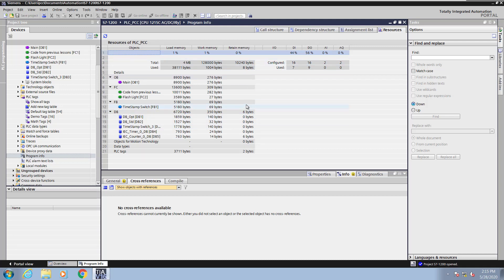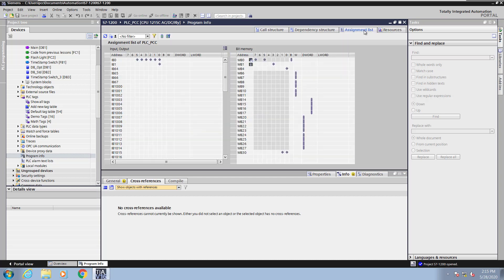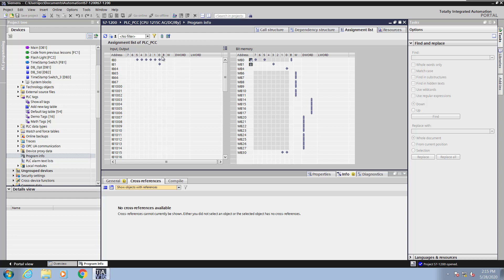Next I will select the assignment list tab. This is where you can see where your inputs, outputs, and M memory locations have been used within your PLC program. You can hover over a particular address, and it will display the tag name that's being used for that address. You have bit access, byte access, word access, double word access, and L word access.